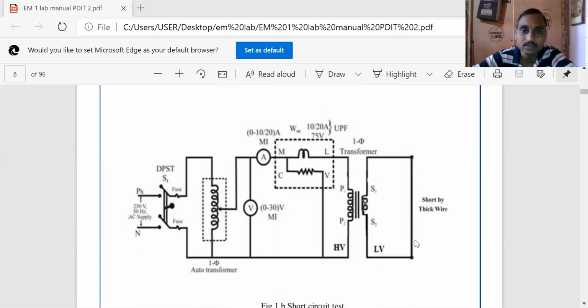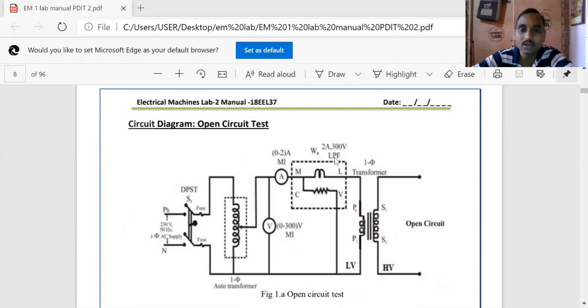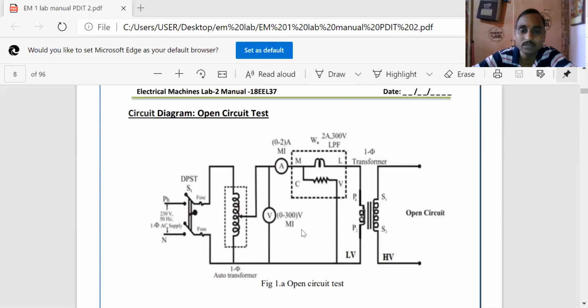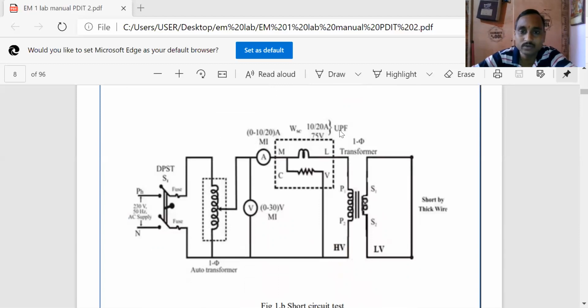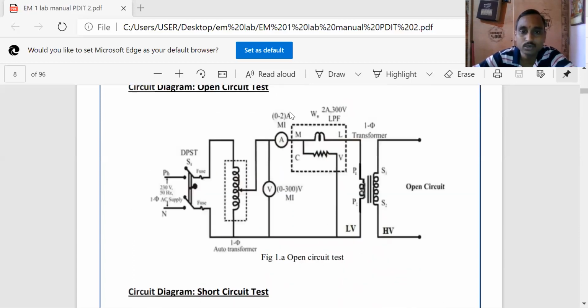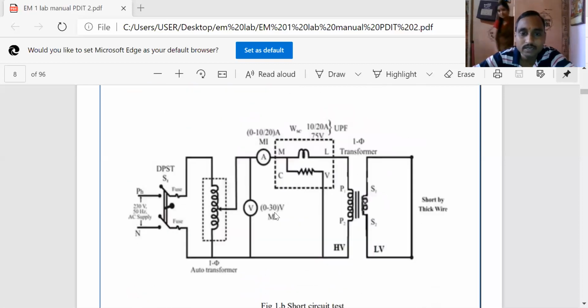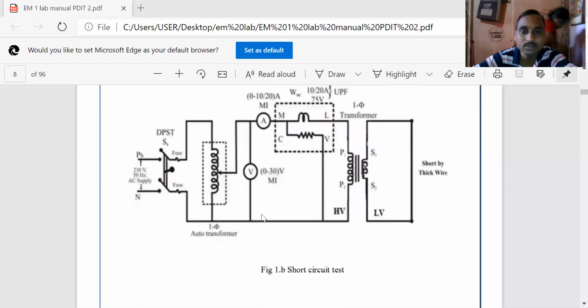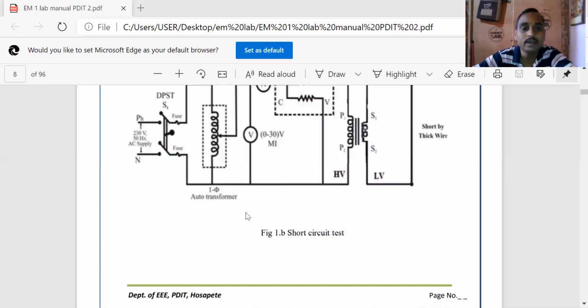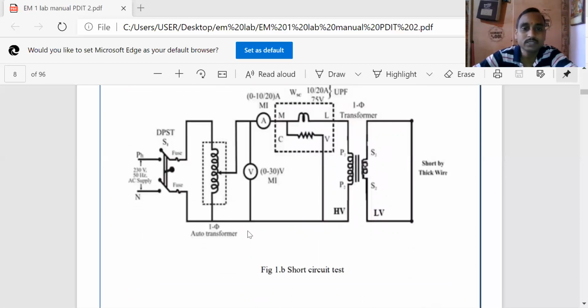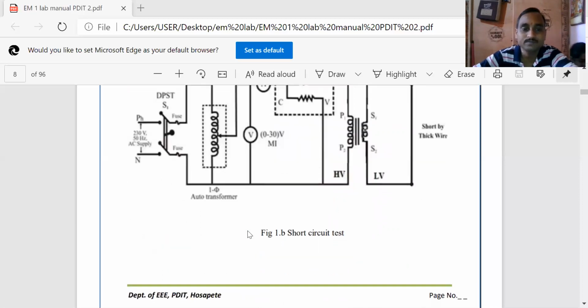or thick wire. Here, we are using a low power factor wattmeter in the open circuit test, and a unity power factor wattmeter for the short circuit test. So that is going to be changed, and the current range of the ammeter is also going to be changed. Here it is 0 to 10 ampere in the short circuit test, and 0 to 2 ampere in the open circuit test. The voltmeter rating is 0 to 300 volt in the open circuit test, and 0 to 30 volt in the short circuit test. Okay, and this is about the short circuit test of a transformer.